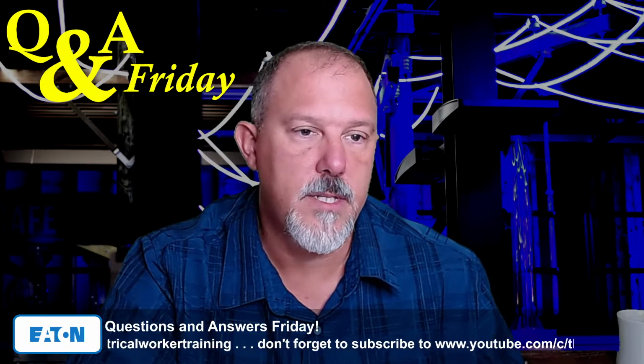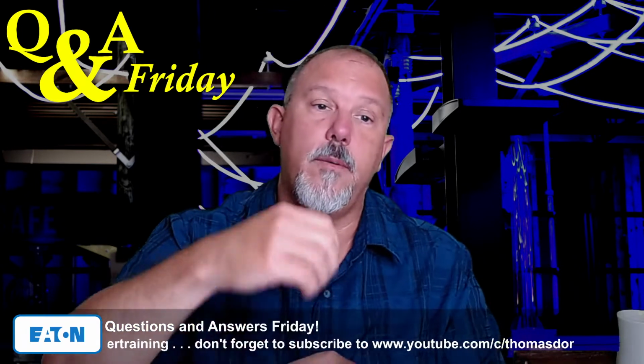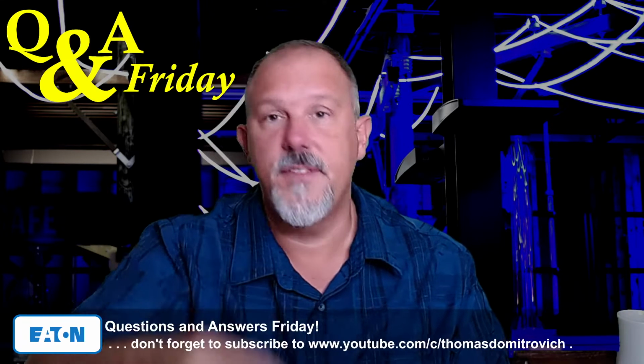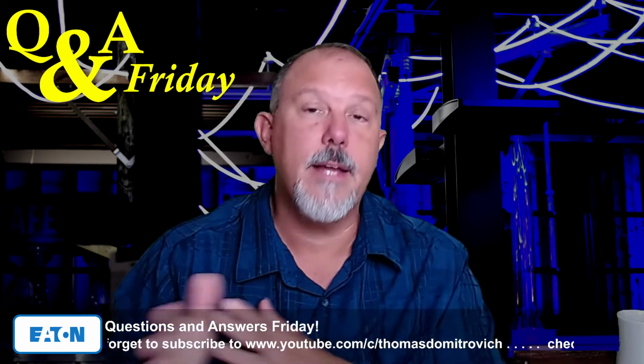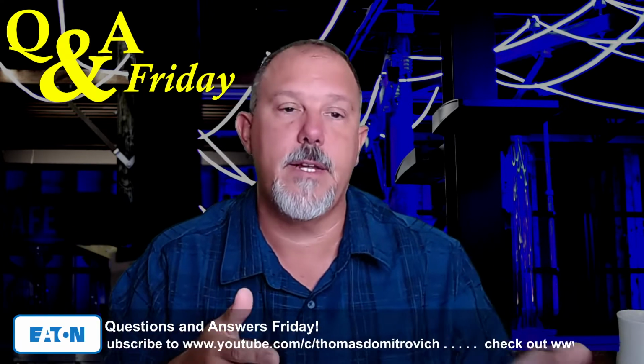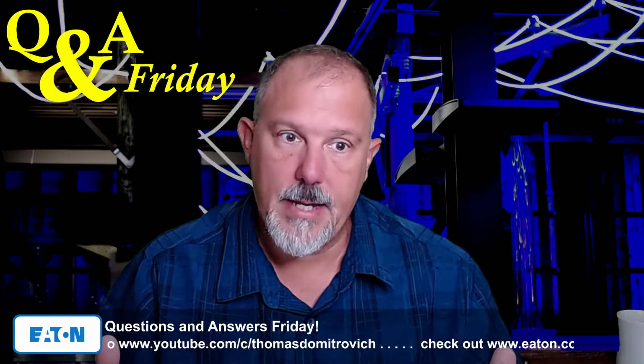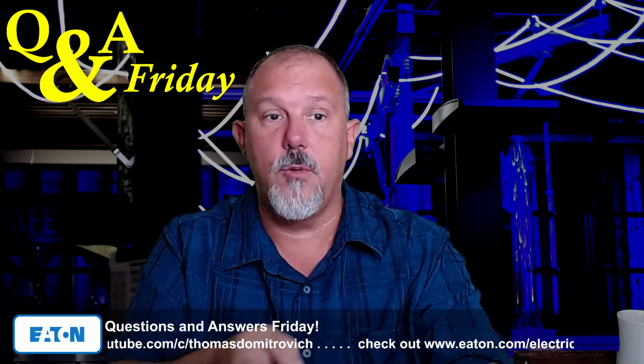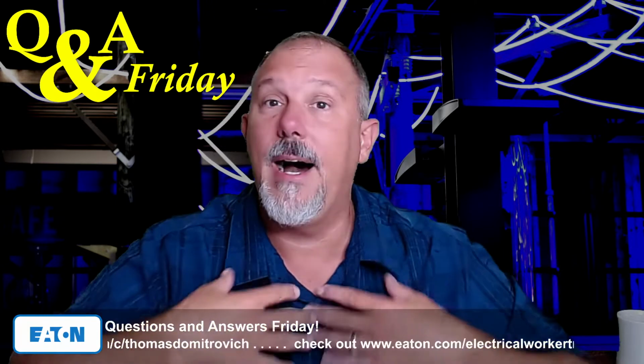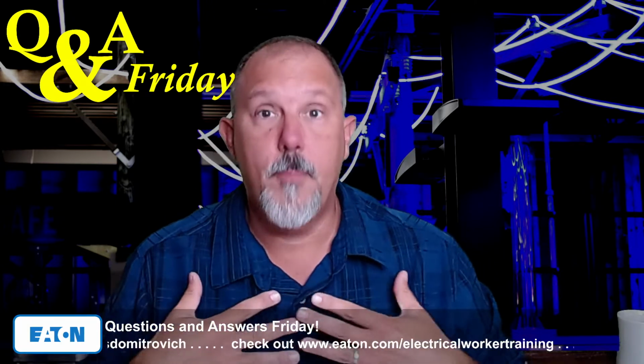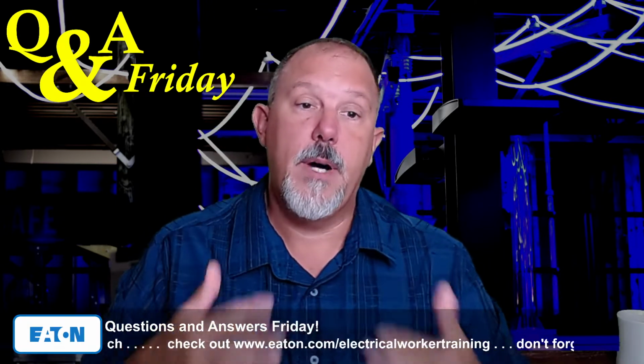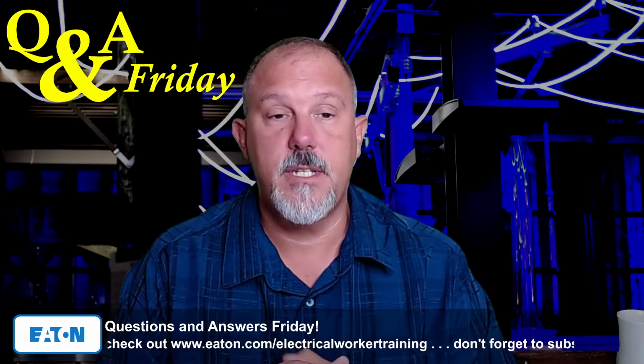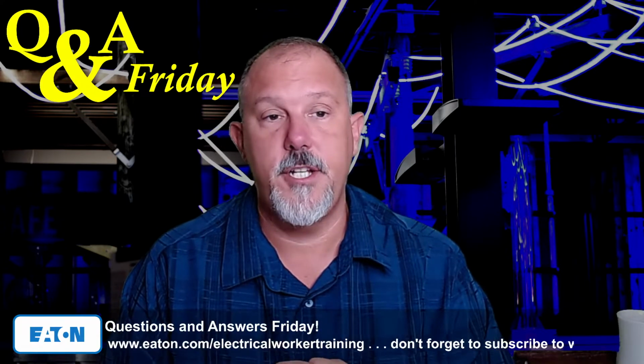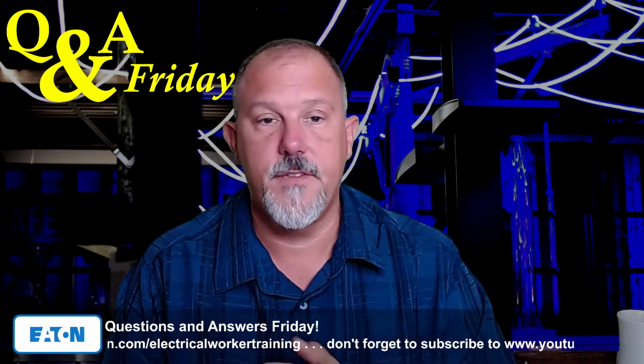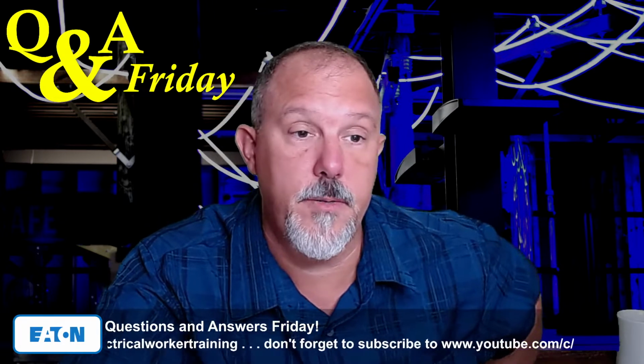It would be more robust and thus more reliable. Remember, though, our equipment grounding conductor is not GFCI protection. So I can't go with just saying, bring an equipment grounding conductor out there and leave it at that. If you wanted to have a debate on whether you should have GFCI or GFPE, I'm open to that discussion personally. But to just sit down and say you don't need GFCI, that it's more reliable than GFCI, I completely disagree with you there. Sorry.